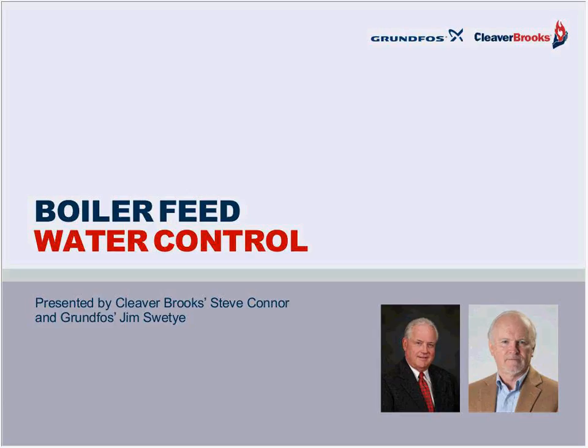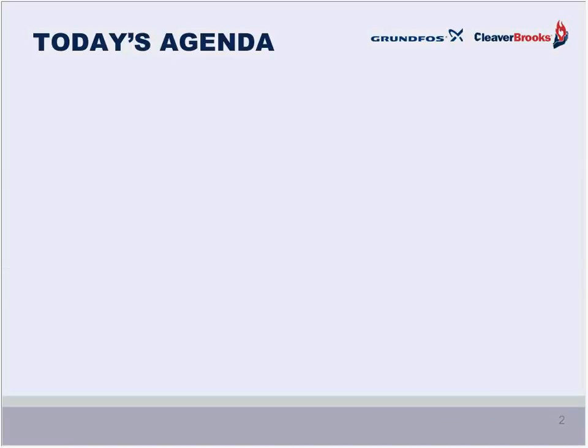...on best practices for feed water control for boilers, especially as it relates to the options that one has for piping, I should say, and pump control, because some ways may be a little bit better than others when it comes to not only maintaining proper level control in the boiler, but also saving energy. So this is what we're going to be covering today.